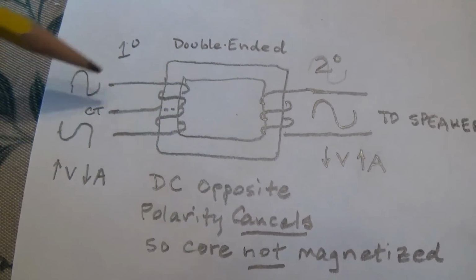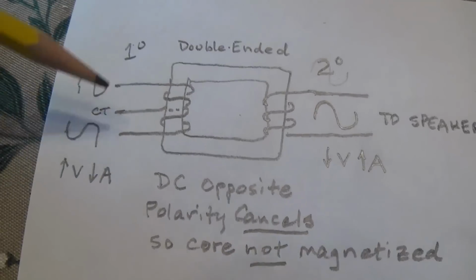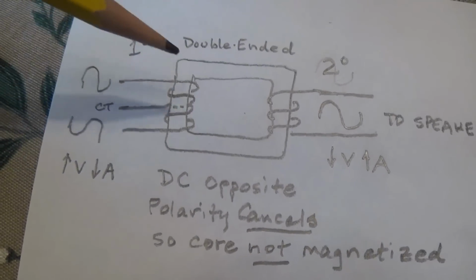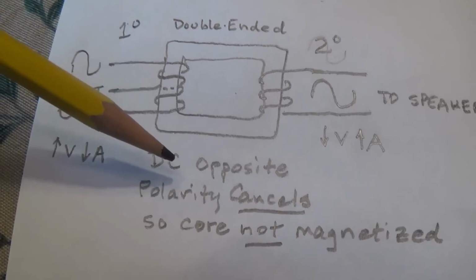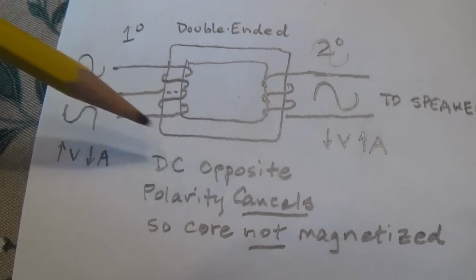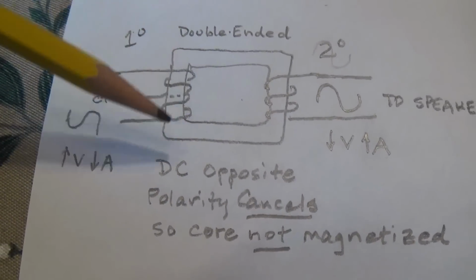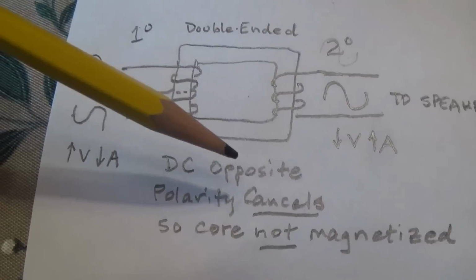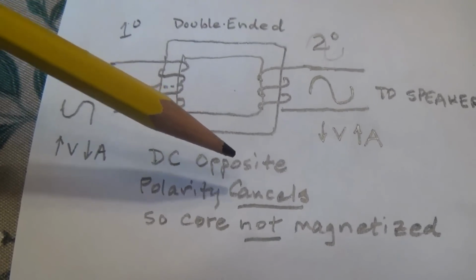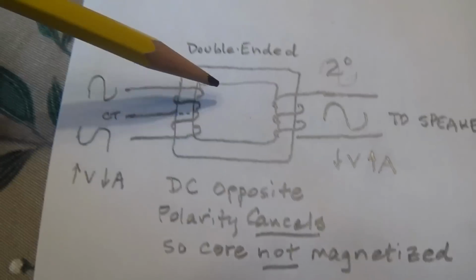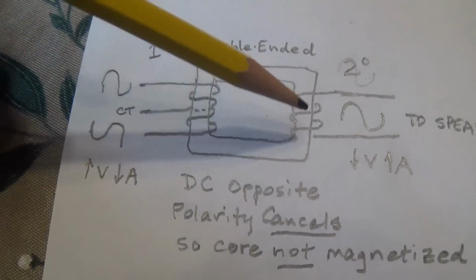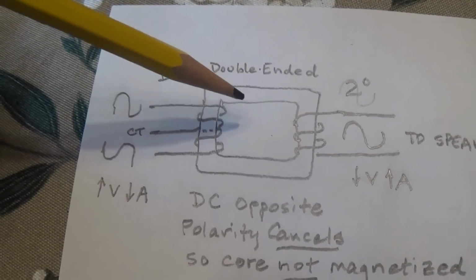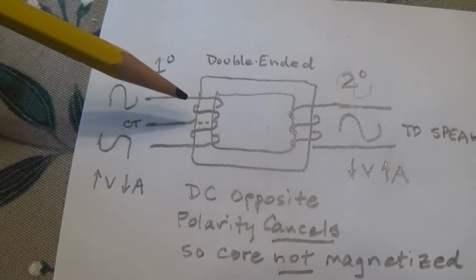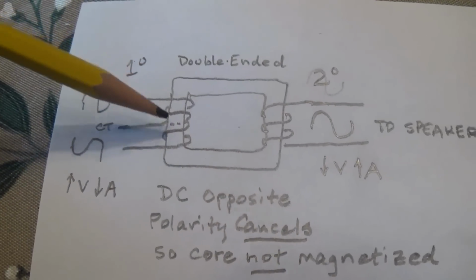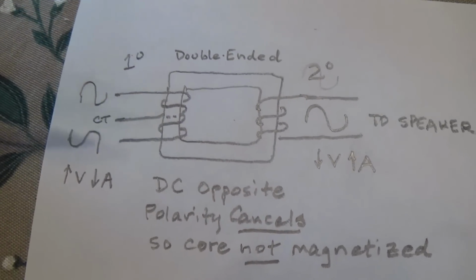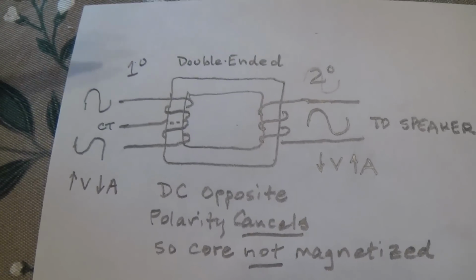But since the DC is also out of phase, the DC polarity cancels out. The opposite polarity of the DC current flowing here will cancel out, and the core will not be magnetized at all. Therefore, you can use a smaller core and fewer windings than with a single-ended transformer, for reasons we'll see in just a minute.